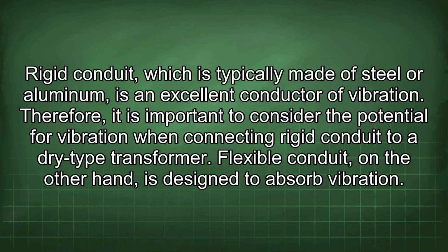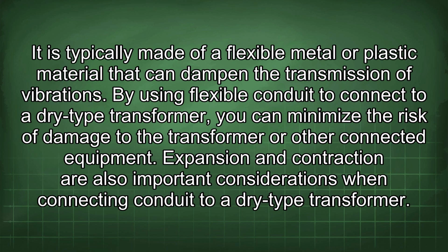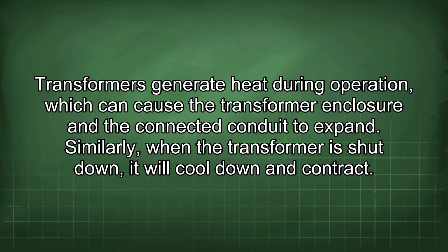Flexible conduit, on the other hand, is designed to absorb vibration. It is typically made of a flexible metal or plastic material that can dampen the transmission of vibrations. By using flexible conduit to connect to a dry-type transformer, you can minimize the risk of damage to the transformer or other connected equipment. Expansion and contraction are also important considerations when connecting conduit to a dry-type transformer. Transformers generate heat during operation, which can cause the transformer enclosure and the connected conduit to expand. Similarly, when the transformer is shut down, it will cool down and contract.